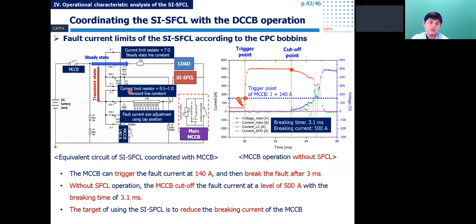This is the equivalent circuit of the testing system. The fault current and the DC circuit breaker operation without the SFCL operation will be confirmed first. You can see the circuit breaker can trigger at 140 ampere and break the fault current after 3 milliseconds. The target of using the SFCL is to reduce the breaking current of the circuit breaker.